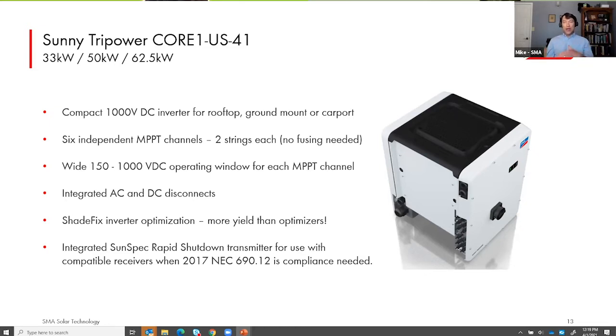The DC input design, those 6 independent tracking channel inputs, you can see on the 3rd bullet point, each of those has a very, very wide operating range from 150 volts up to 1,000 volts DC. So whatever module type you may be considering using, wherever the install location is for the temperature range, you should have a wide range of appropriate string lengths.